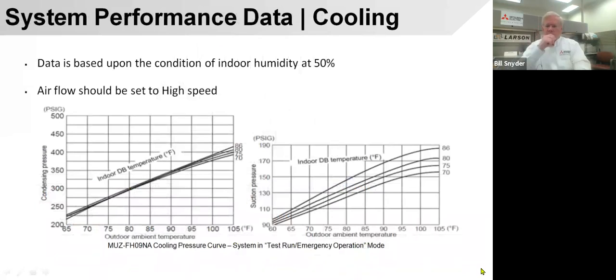This is a test diagram. This is not to help you charge the system. This is just to see if it's working properly. If you throw the system into test run or emergency mode operation, on a P series, the test run will be a dip switch on the outside. On an M series, it's a button on the indoor unit. It's an EO switch, an EO SW. It's an emergency operation switch. You throw it into the emergency operation or test mode and make sure the fan is on high.